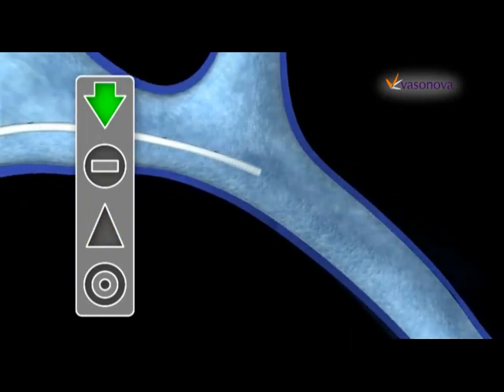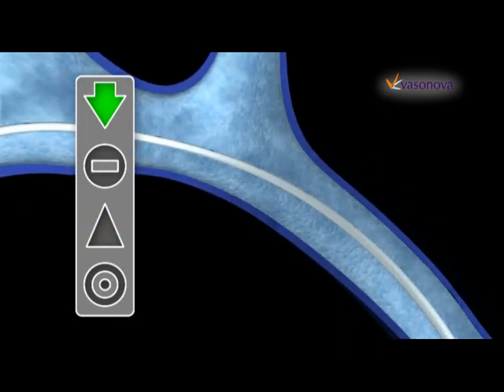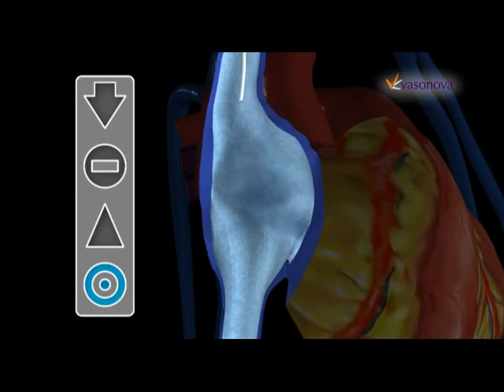If the catheter tip inadvertently advances beyond the cavoatrial junction and into the right atrium, the orange 'do not enter' sign illuminates, indicating that the catheter tip is now moving away from the heart. As the catheter is withdrawn back to the proper location, the blue bullseye appears again.